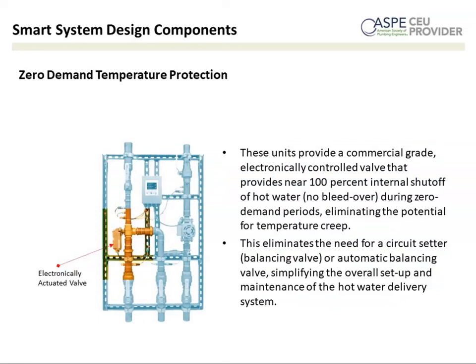So this is a little bit around zero demand protection. With this particular valve, and with a lot of these valves now versus traditional mixing valves, these valves have 100% hot water shutoff. Essentially, consider a low or no demand situation, let's just say in a nursing home, or any facility where overnight there's no draw on the system, and the temperature continues to increase.